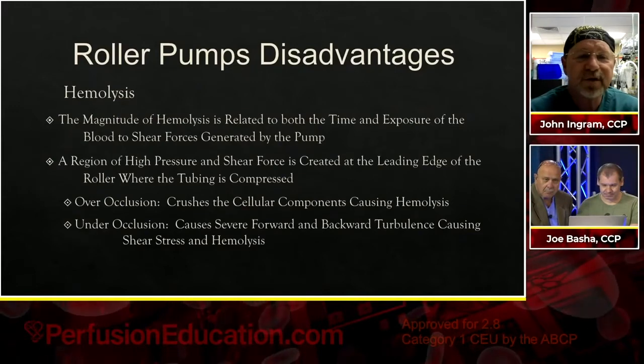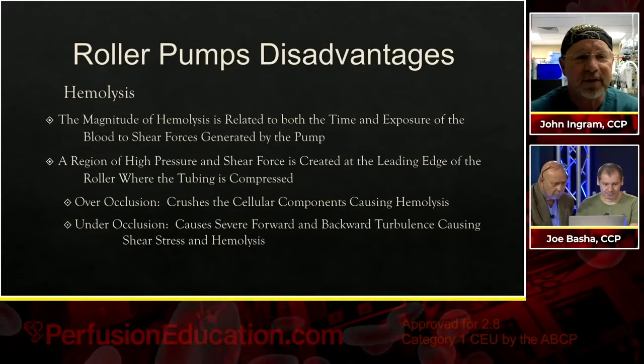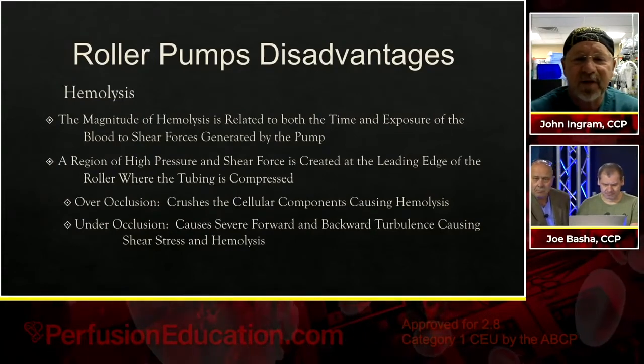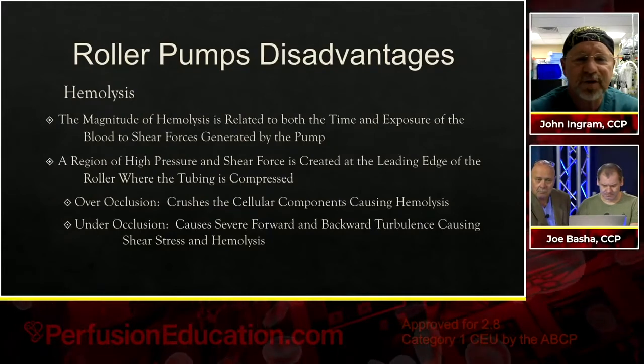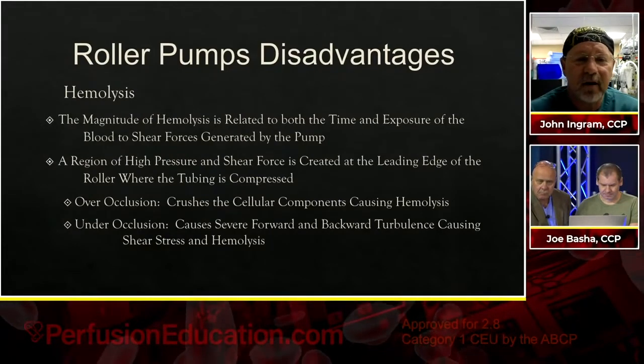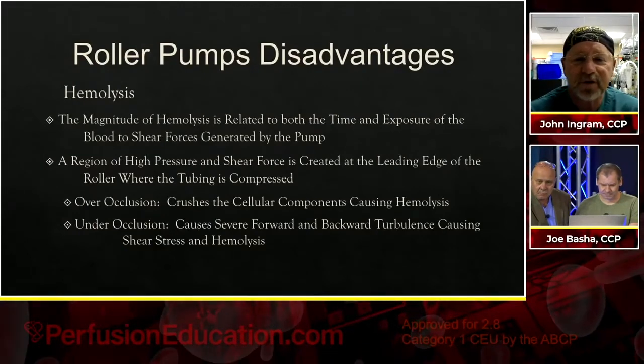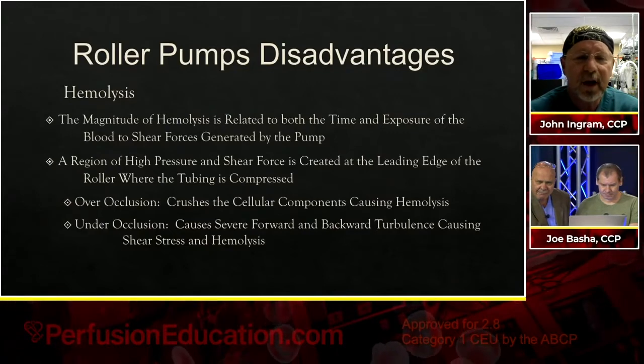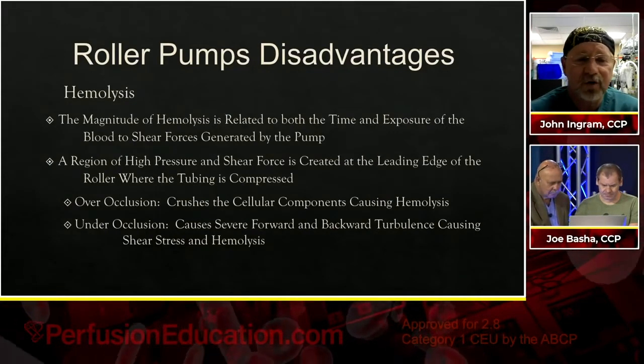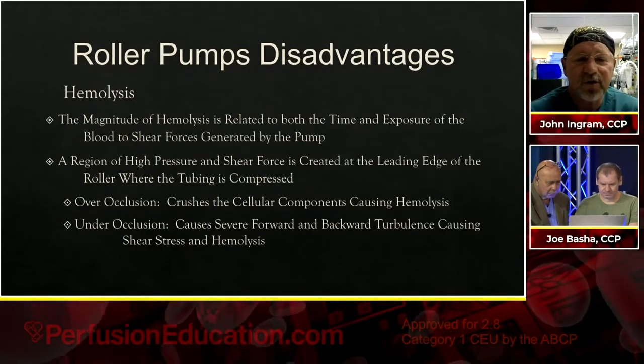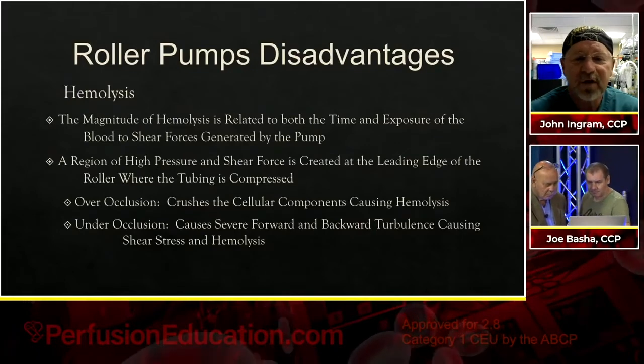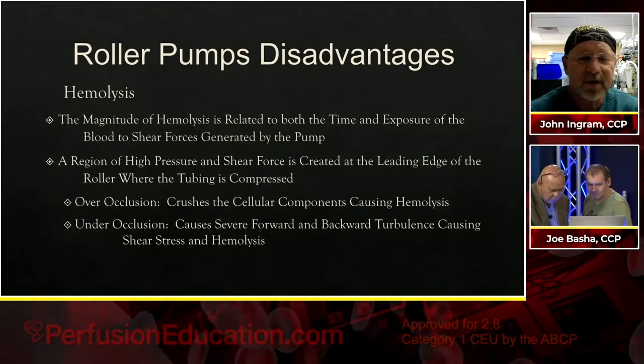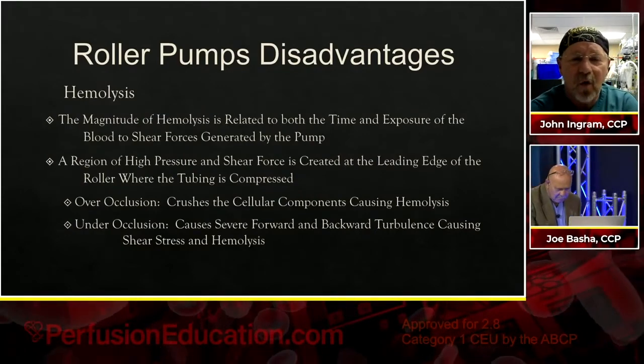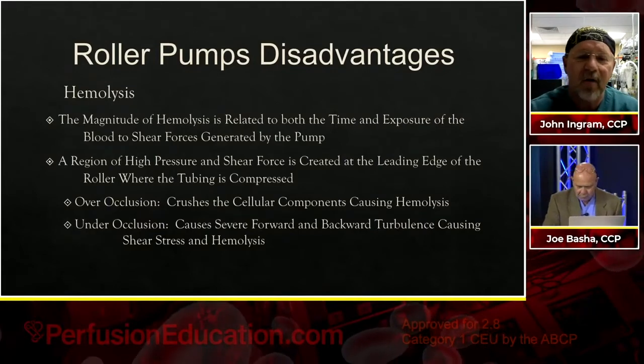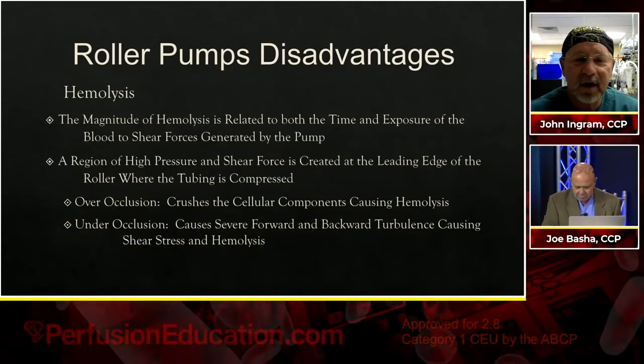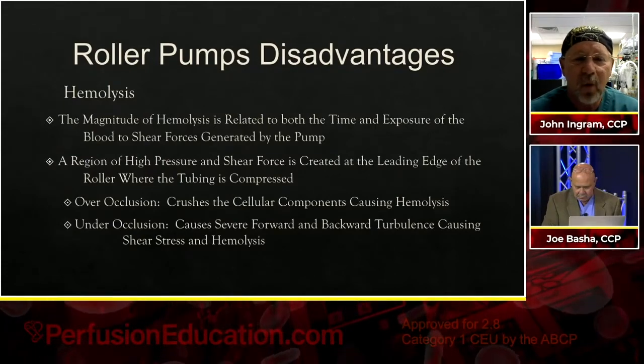Yep. So another disadvantage would be that it can be implicated in hemolysis. Well, the magnitude of the hemolysis is related to both the time and exposure of the blood to the shear forces generated by the pump. That's actually true of any kind of pump. There's a region of high pressure and shear forces created at the leading edge of the roller where the tubing is being compressed. Now, you can have an over-occlusion, you can have an under-occlusion. If you have an over-occlusion, the roller will crush the cellular components inside the tubing, causing hemolysis. This is why you don't want a 100% occluded roller pump, and why I showed you those occlusion techniques that allow for the ever so slightly gap so that it's not completely occluded against itself when the roller comes by.